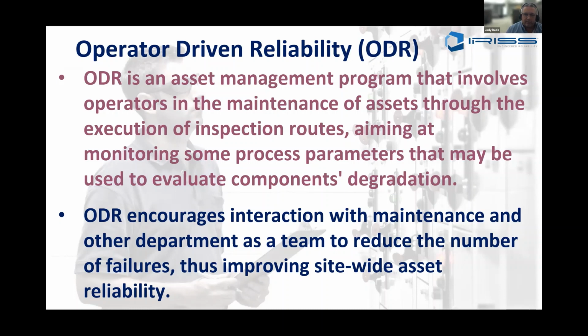The ODR concept is like another maintenance strategy known as total productive maintenance, TPM, which was developed in Japan in the early 1960s. ODR uses operators to observe the running condition of their equipment and to make minor corrections if they're competent to do so. By proactively identifying problems, operators can eliminate or reduce failures, thereby increasing reliability. They perform such tasks as cleaning, minor adjustments, lubrication, and simple preventative and corrective tasks traditionally handled by a skilled maintenance technician. These tasks represent a departure from the operator's traditional role as just an equipment operator.